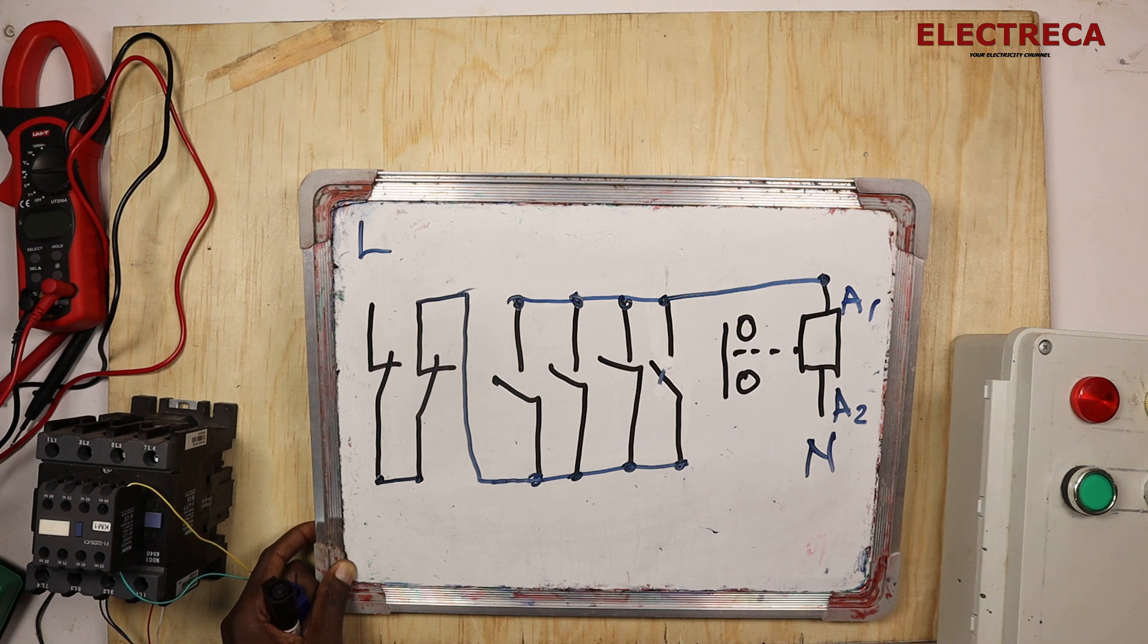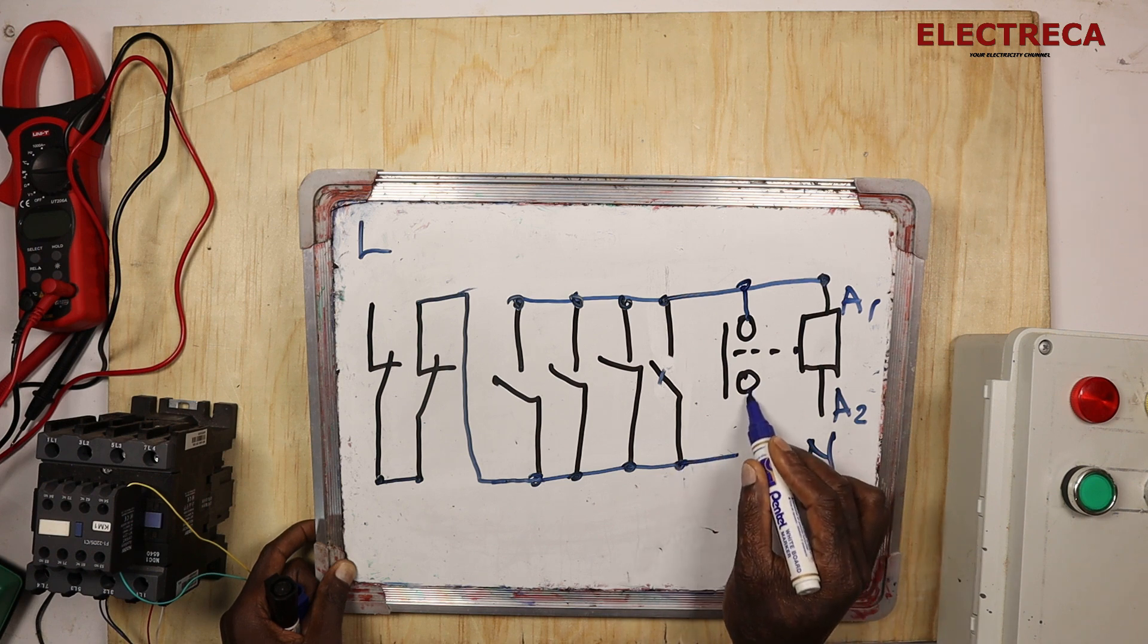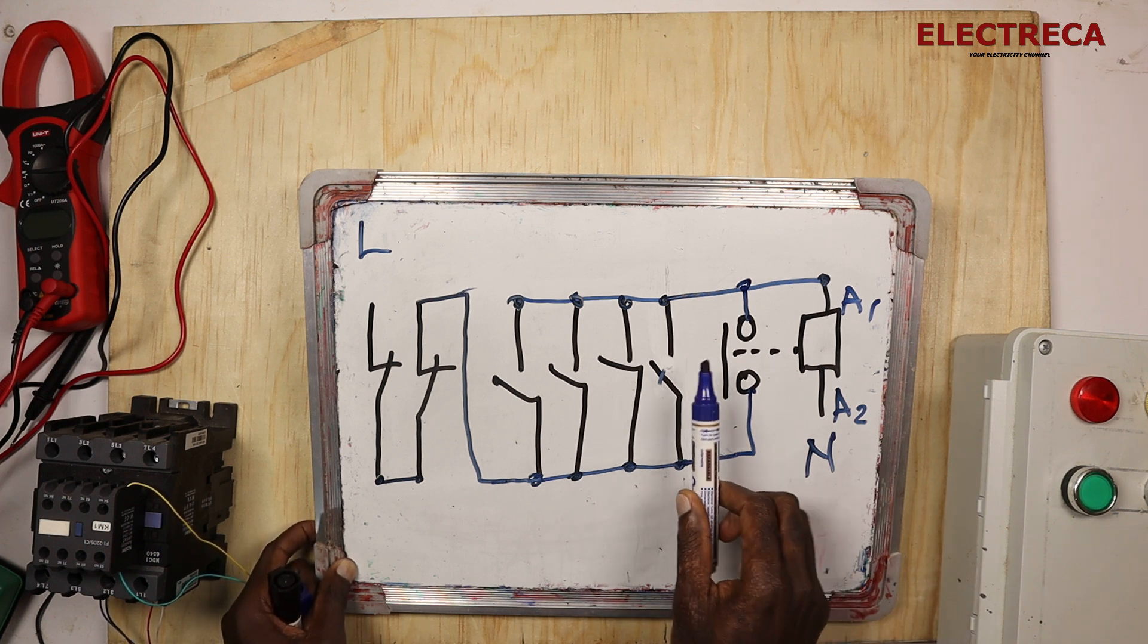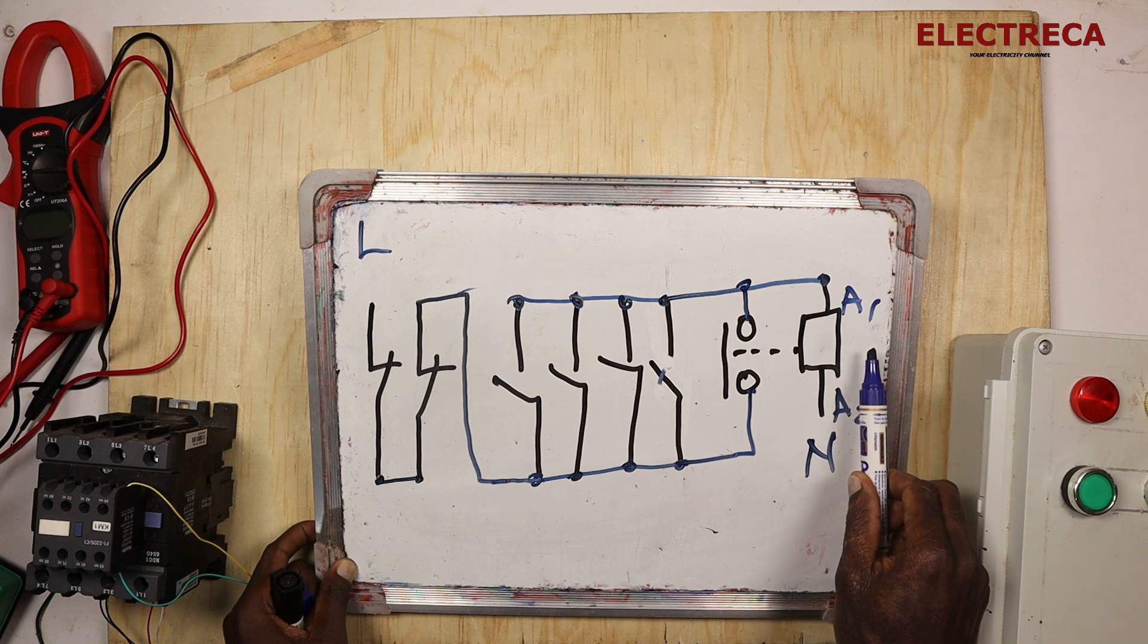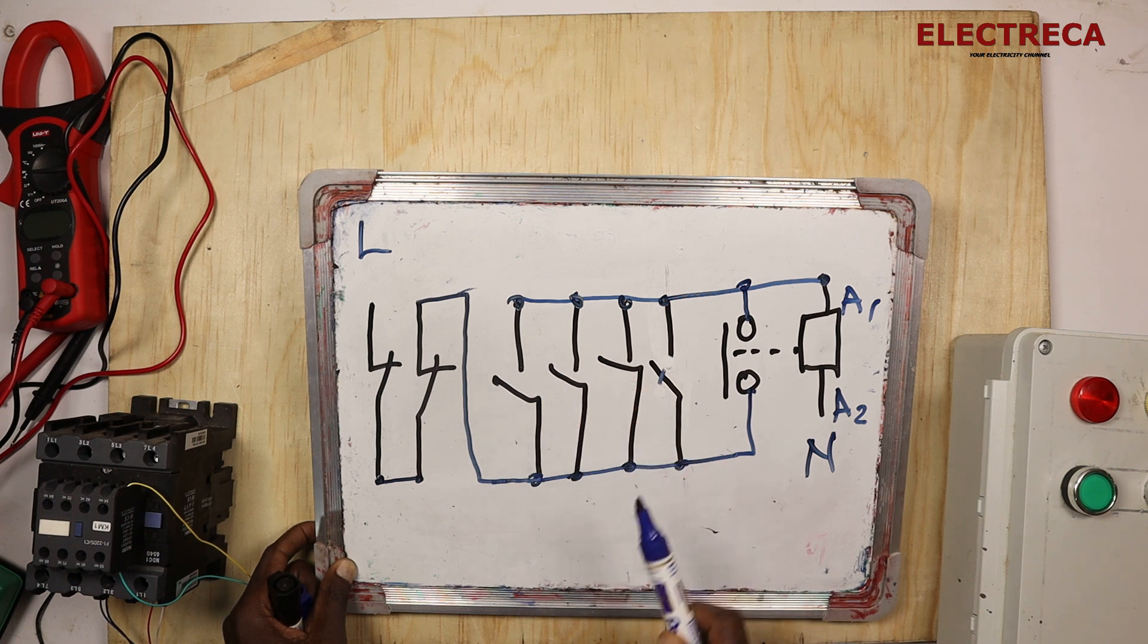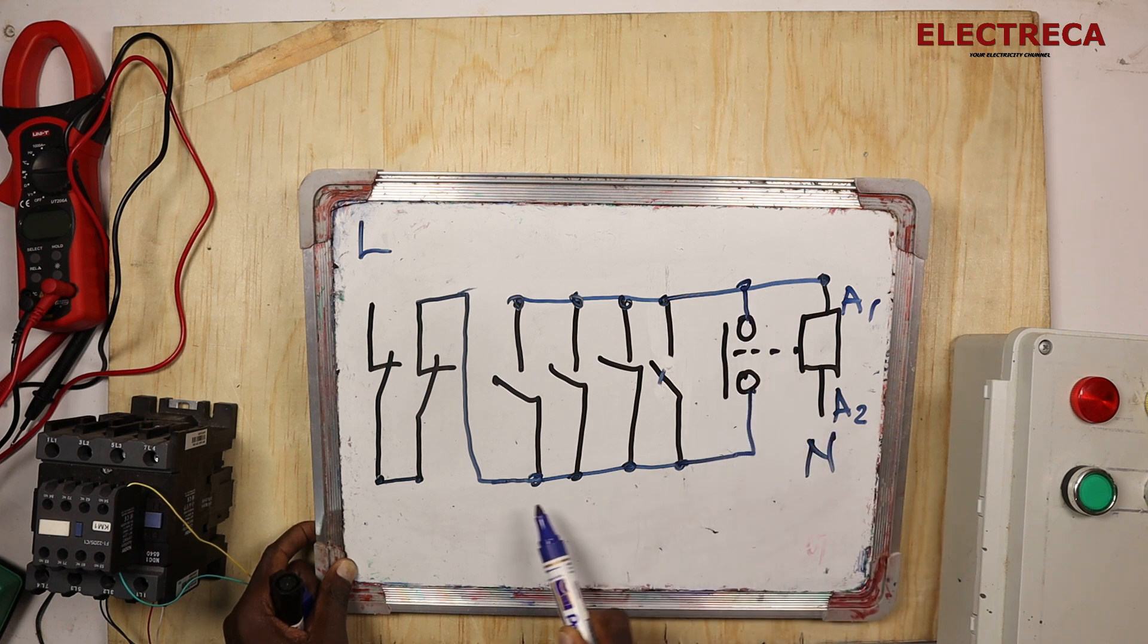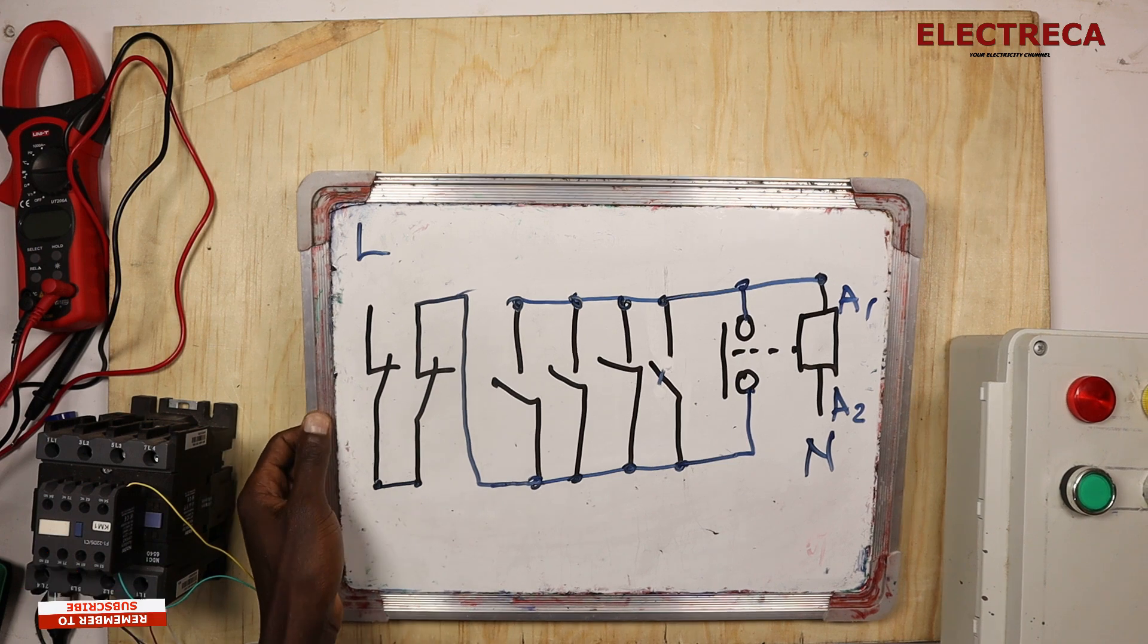It will not hold because we've not connected that one, so what we do we will connect here and then this side we connect right here. So once you close this contact here, one of the four contacts, the contactor will energize. Now after you release this button here, because this will be closed, our current now will get the second path. As simple as that.